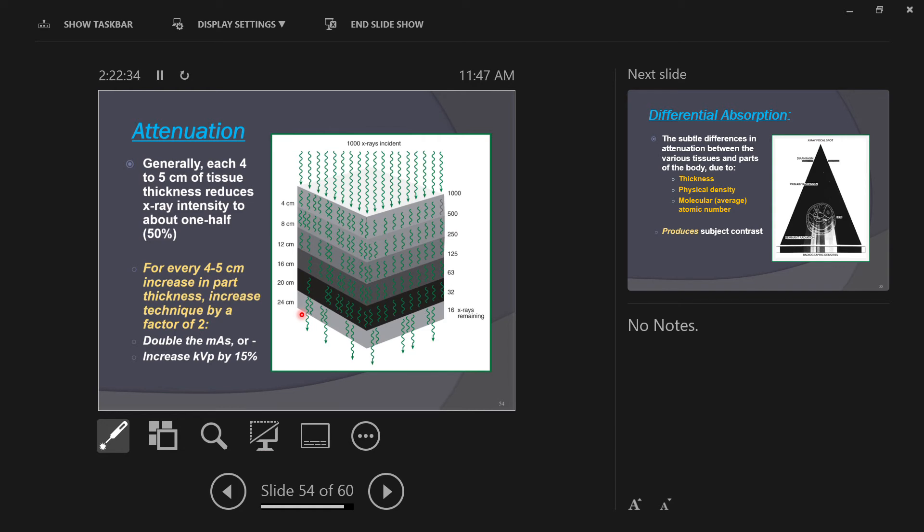69 KVP. Good. So, that is how taking 15% of 60 gives you 9, and then you just add the 9 to 60 and make 69 KV. Or you can take 60, multiply it by 1.15, giving you the full 60 plus the 15%, 69. Doesn't matter how you do it. Both ways are equivalent.